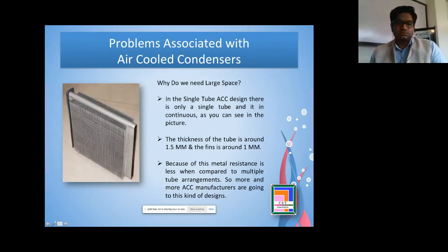It's a good design, and a lot of heat exchanger manufacturers are going for this kind of technology, because there is less steam side pressure drop, and there is also less air side pressure drop. So we save on power, and we get better efficiency compared to the individual fin tube.